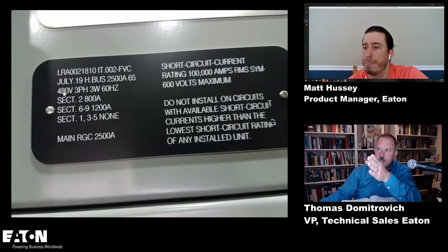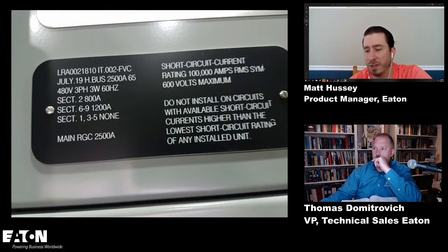So then we have the vertical sections, 800 amps, 1200 amps. It looks like there's 9 sections in this. And it says section 1, 3-5 none. What does that mean? Yep. So section 1 probably doesn't have any vertical bus. Largely it's probably because there's a main. So that main might be connected directly to the vertical or to the horizontal bus. And then 3 through 5 would be maybe utilized as like a big relay structure, or maybe a large drive, which also could connect directly to the horizontal bus.